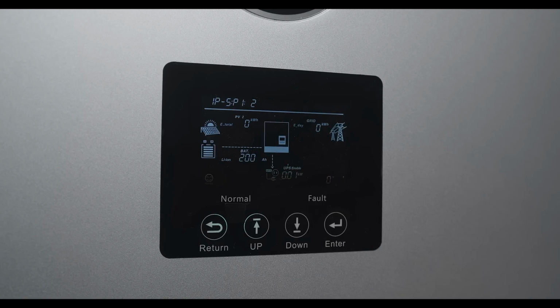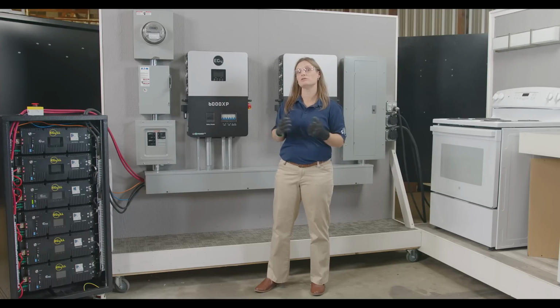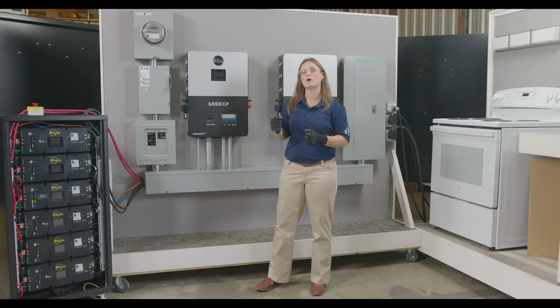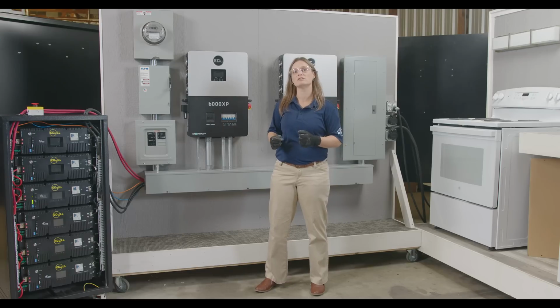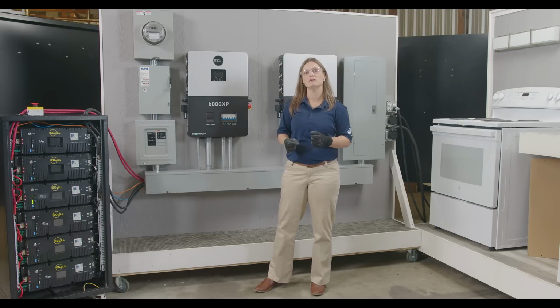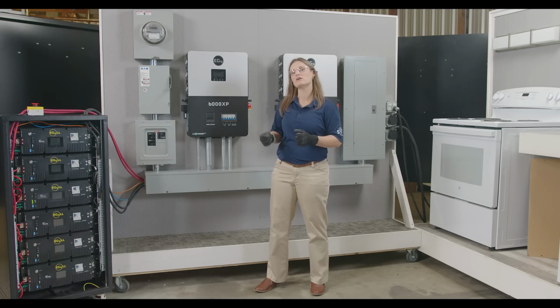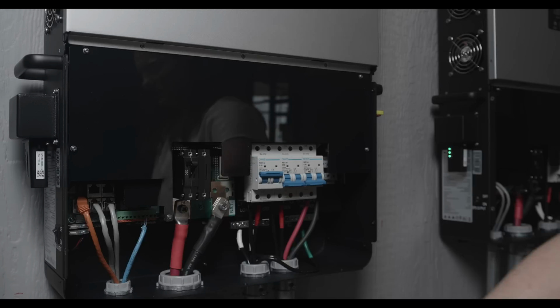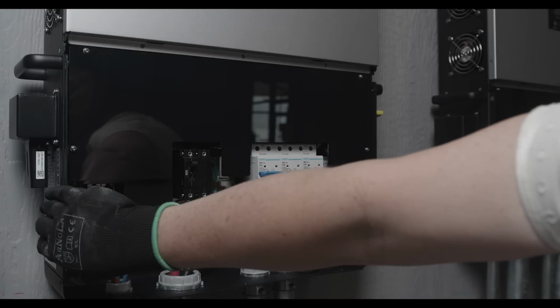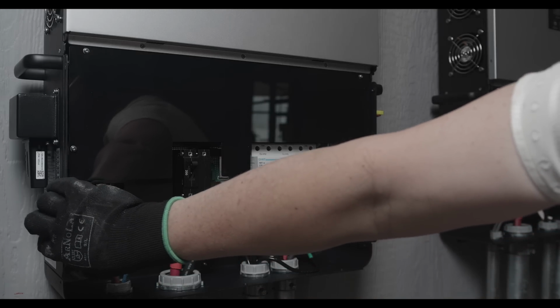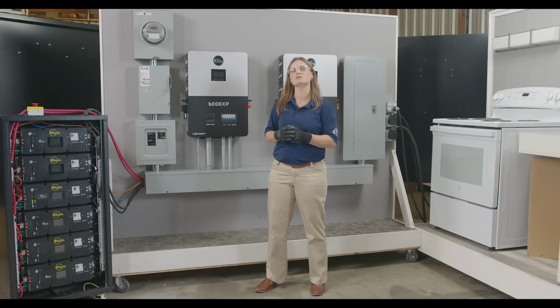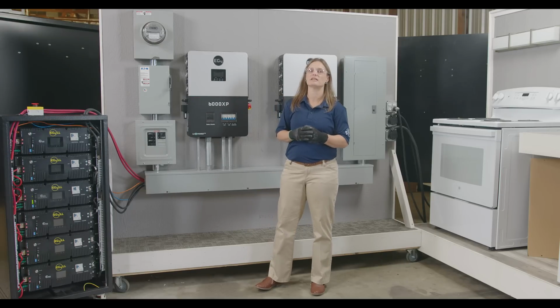All right, the moment of truth. To determine the proper host and slave definition of your inverters, if connected in parallel, turn on the power and the EPS output on the host inverter first to designate it as host. Then, turn on the EPS output on the rest of the inverters paralleled past the host using the switch on the side of the unit to define them as slaves.